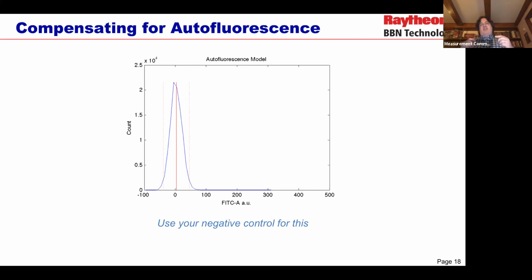So the instrument is giving us these fluorescence values through interpreting a voltage on the detector. And so there's just a little bit of noise in that. And on a range of, say, 10 to the 5th, going up and down a couple hundred is not unusual. But you can see there's a tiny little nudge to the right here.